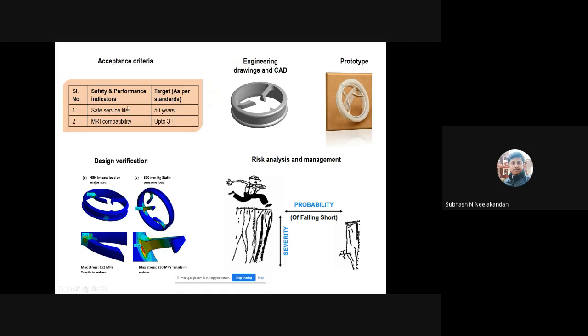For example, for a medical device which is implantable, inside the human body, in general almost all cardiovascular implants are designed for 50 years. So the safe service life is 50 years bare minimum. Whichever cardiovascular implant we are going to develop should meet 50 years if that is our target.